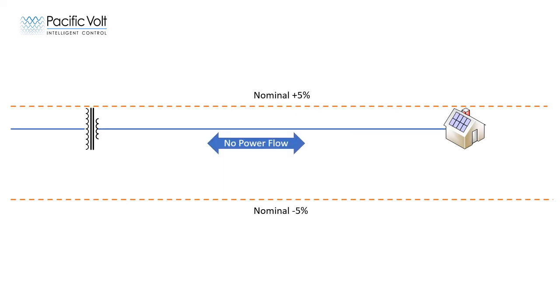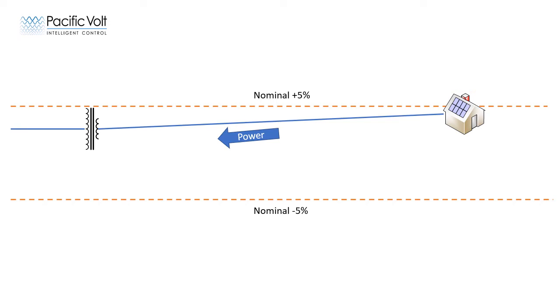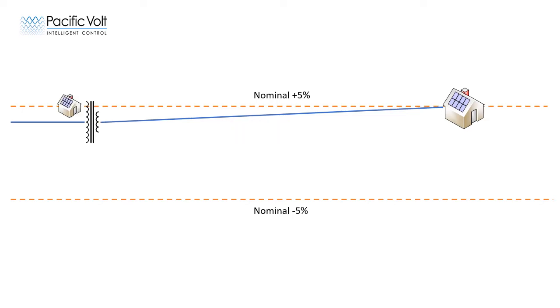If the energy consumption of the building is equal to the energy the solar is generating, there is no voltage rise or fall. This is because there is no power flowing on the secondary. If excess solar power is produced, the voltage at the building will need to be higher than the voltage at the transformer in order to overcome the impedance and get the energy to flow backward onto the feeder. The voltage on the medium voltage side of the transformer will also rise slightly. With more and more solar on the feeder, the voltage on the medium voltage feeder also begins to rise.